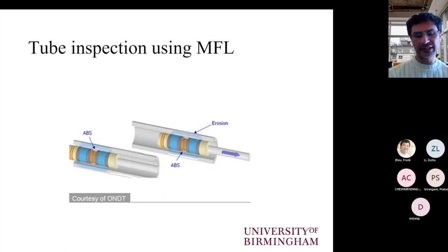This is a diagram that shows the positions of the different coils when we are inspecting tubes. So we have the absolute coil in the center, and then we have the differential coils on the side, which are responsible, as I said earlier, for detecting smaller defects. The differential coils are usually generating signals that are subtracted from one another. So if there is any difference in the reading of one coil, then that will give us a difference to the subtracted value, the subtracted sum of the two coils, and that will be our signal. In some cases, it can be in addition, but the most common approach involves the two differential coils subtracting the value from each other.